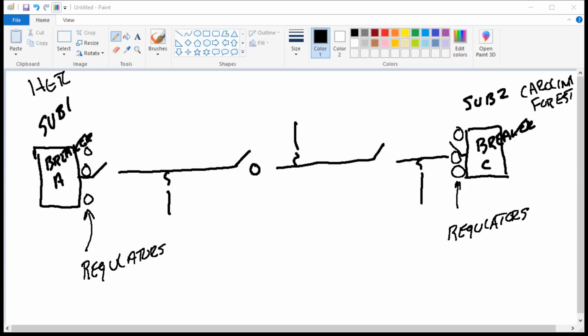I'm sharing a screen over here, and we're going to be talking about doing load transfers between substations on a feeder circuit. It's not really something you're going to be doing every day, but some systems, and I know Santee Cooper did it often, seasonally, will move open points around and try to balance out load on different circuits and different breakers. So they're evenly distributing load between substations and breakers. They'll move open points and close other ones to balance that load out. And also during the course of switching, if you need to get line clearances, which we've talked about before, you'll have to do these in situations.